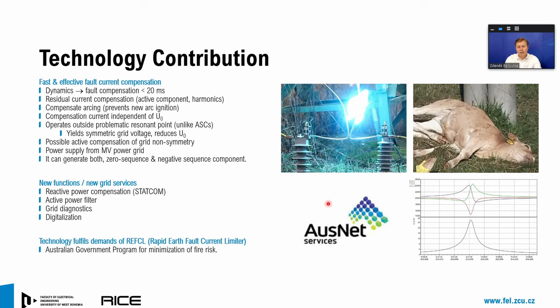The compensation current which we are generating has an arbitrary shape and is independent of the zero sequence voltage. We are operating the device outside the problematic resonant point, which improves the symmetricity of the grid voltage and reduces the zero sequence component under trouble-free operation. We are able to actively compensate the grid non-symmetry. We are getting the power supply directly from the grid, so we can offer full standalone operation. And we are able to generate the positive sequence, zero sequence, as well as negative sequence components of the current.